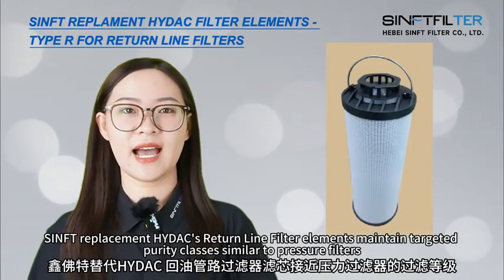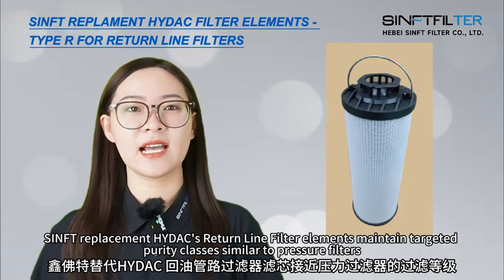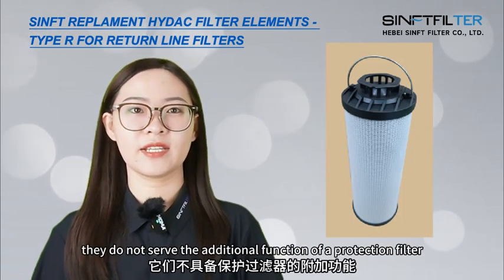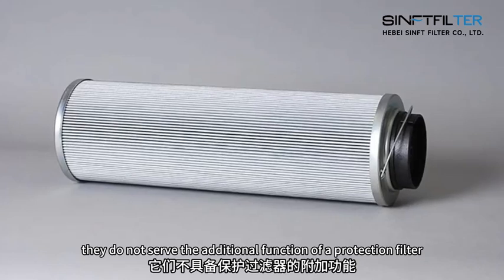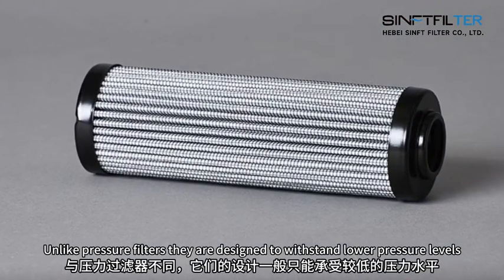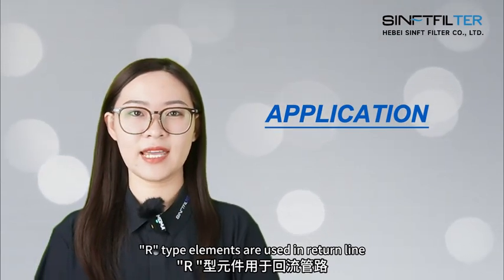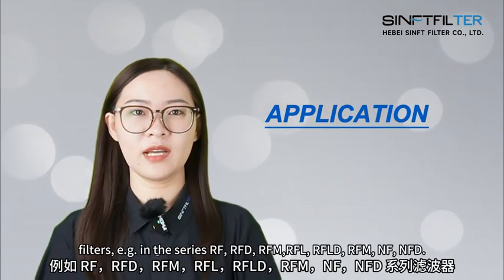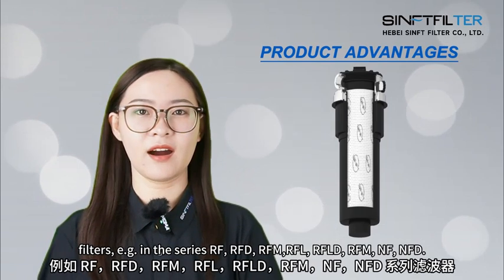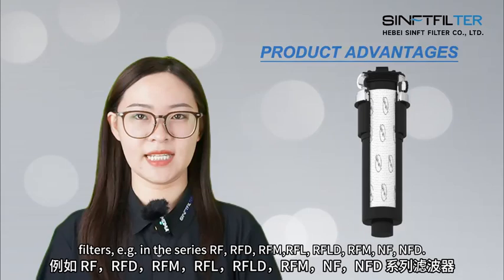Sinft replacement HYDAC return line filter elements maintain targeted purity classes similar to pressure filters. However, due to their configuration, they do not serve the additional function of a protection filter. Unlike pressure filters, they are designed to withstand lower pressure levels. R-type elements are used in return line filters, for example in the series RF, RFD, RFM, RFL, RFLD, NF, NFD.